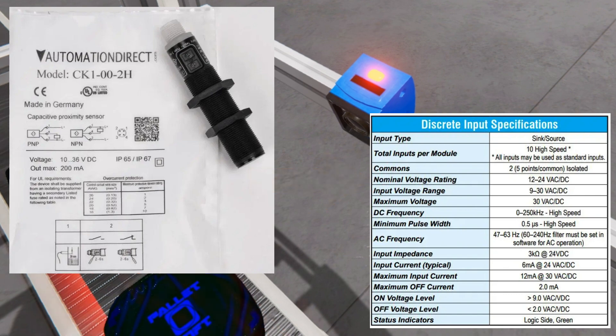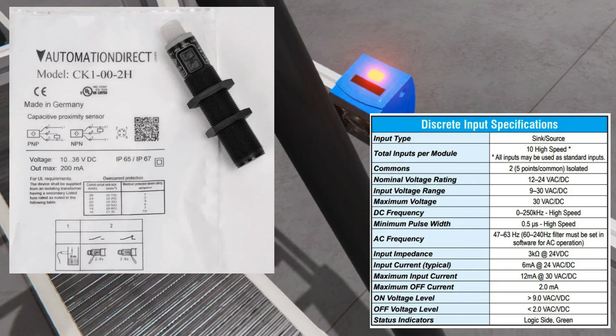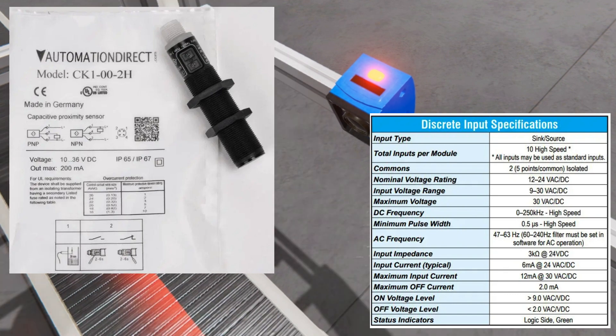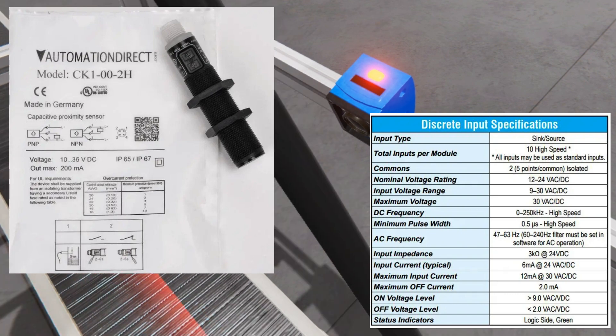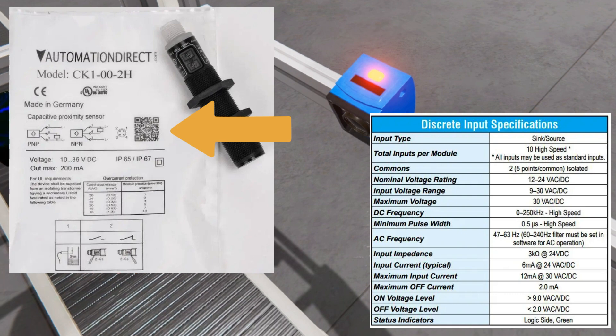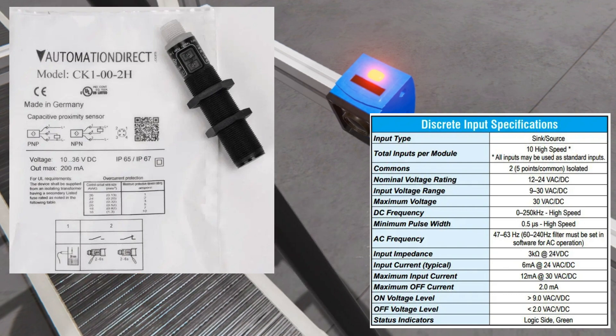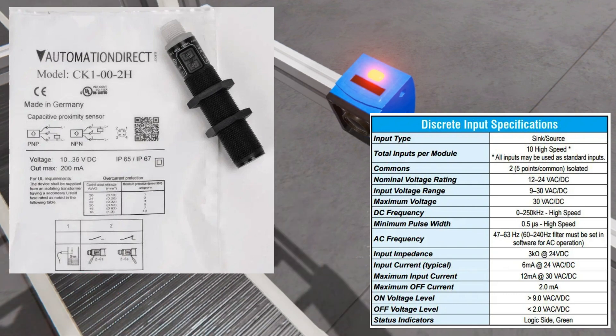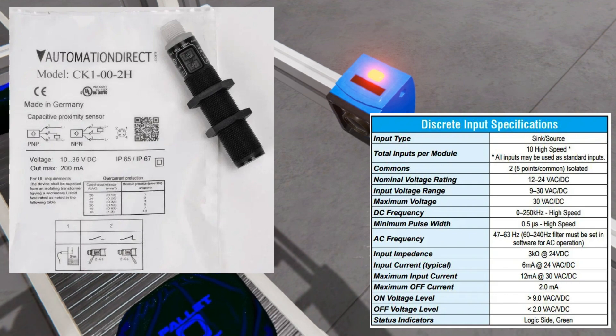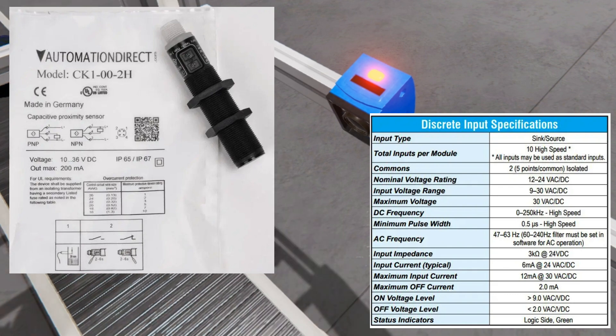Ensure a stable power source that meets the requirements of the switch. Next, connect the proximity switch to the control circuit by connecting the switch's output to the input of the control device, such as a PLC or relay. Follow the wiring diagram provided by the manufacturer. Also consider the wiring distance — excessive wiring distance can lead to voltage drops and signal interference. If the distance is too long, consider using shielded cables or signal amplifiers to maintain signal integrity.